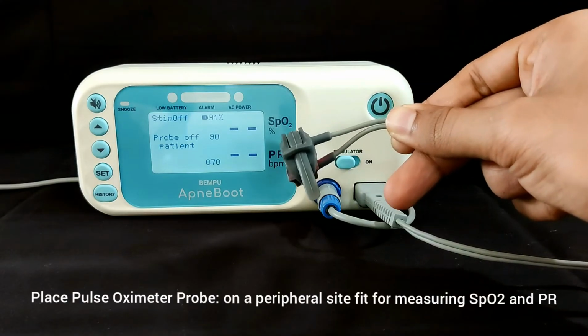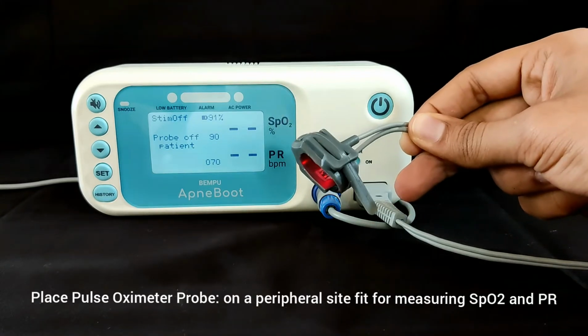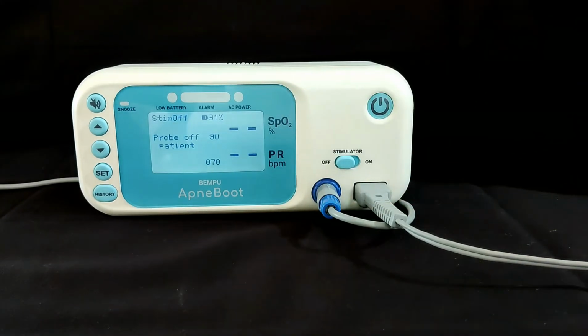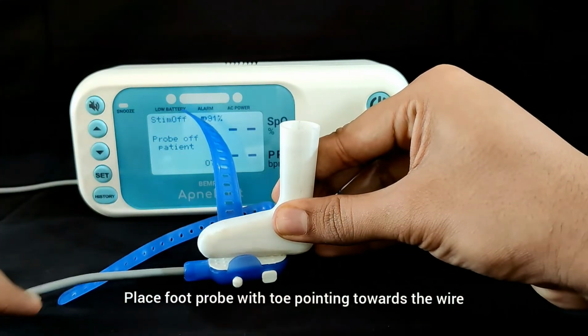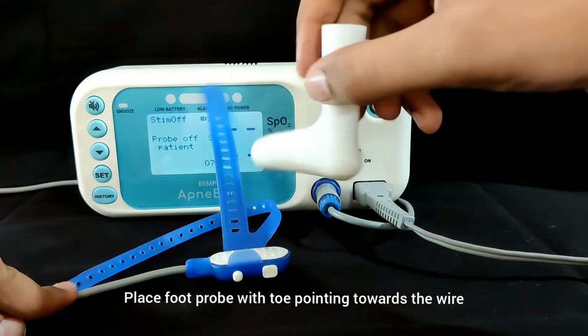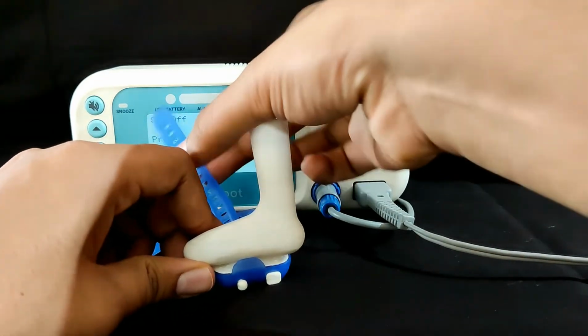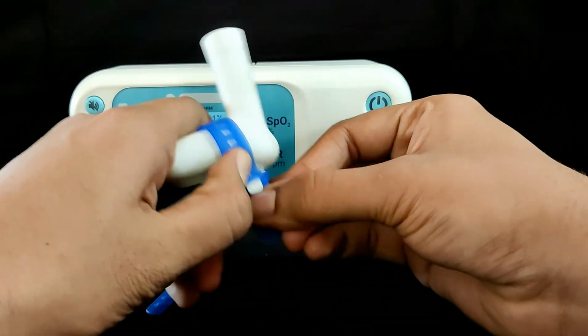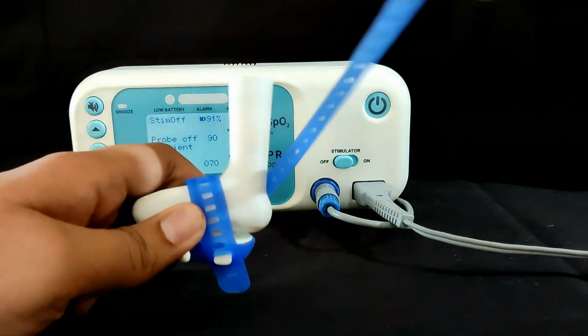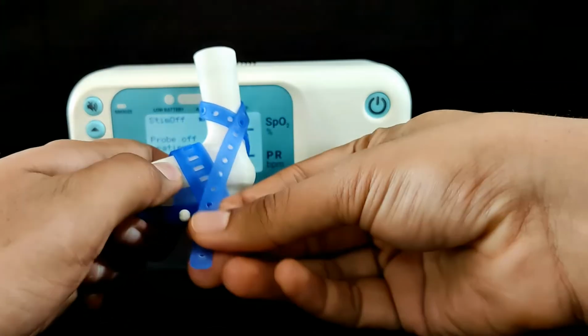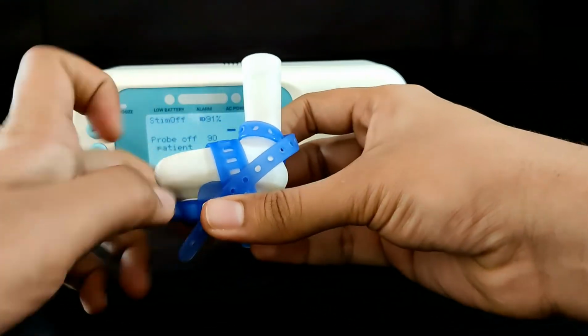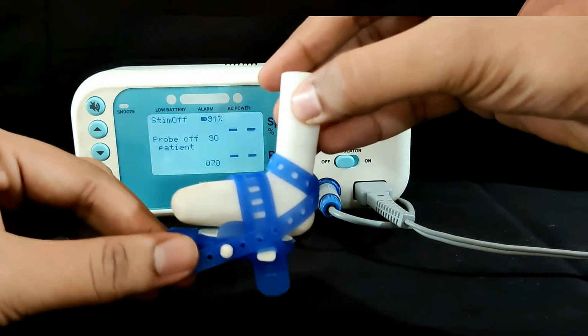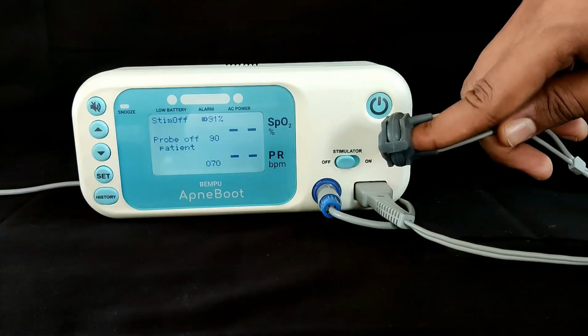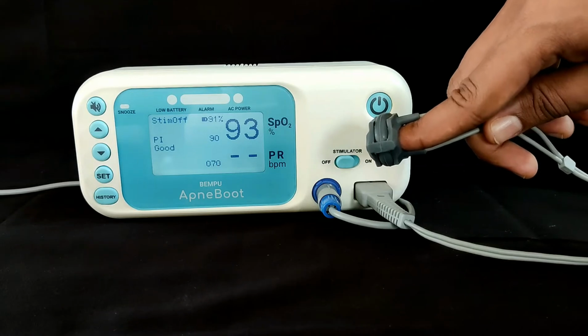Next, place the pulse oximeter probe on the foot or other peripheral site suitable for measuring the oxygen saturation and pulse rate. Now connect the foot probe by placing the toe pointing towards the wire and not the other way around. Wrap the shortest strap like this and plug it in the rectangular notch. Then wrap the longer strap around the ankle and plug it in the round notch. Make sure it is not too tight or too loose. Once connected to the baby, wait for a few minutes for the device to stabilize and start measuring stable values.